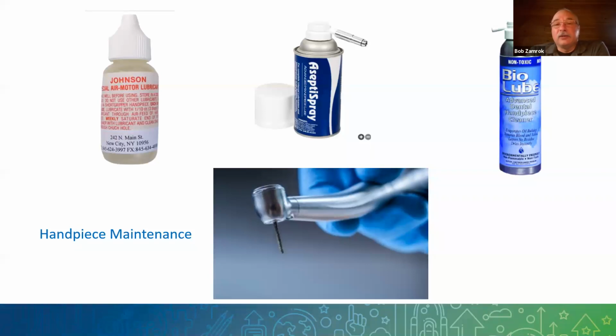Typically, if you have a clean and lube station that you use in your handpieces on a regular basis, you don't need to clean that out or replace the gauze in that, but maybe once or twice a year. If you don't have a good clean and lube station for your handpieces, you're one of the service calls that we get where you've got oil dripping out of a unit, and it's not the unit that's dripping the oil, it's the oil from the handpieces that gets thrown into this collector and it doesn't get changed.